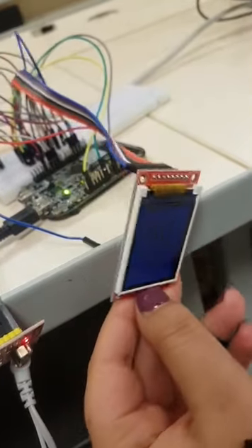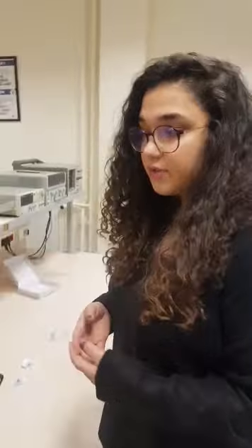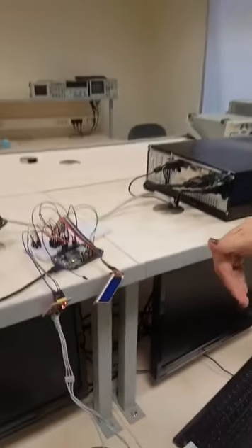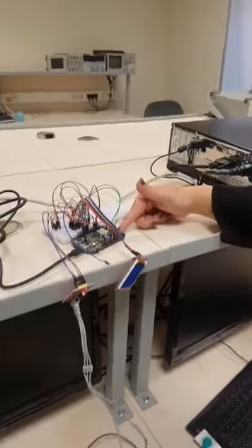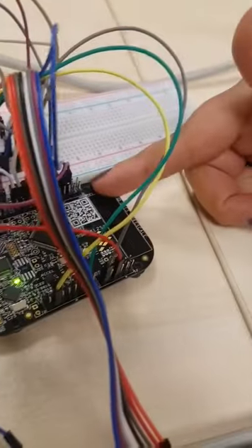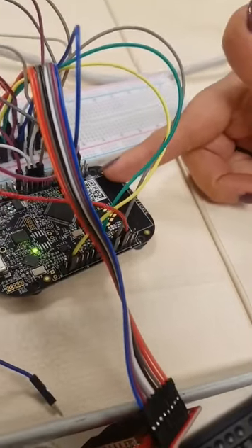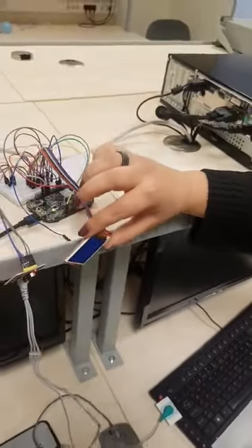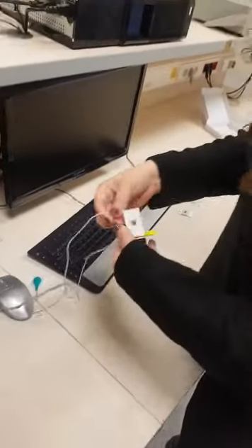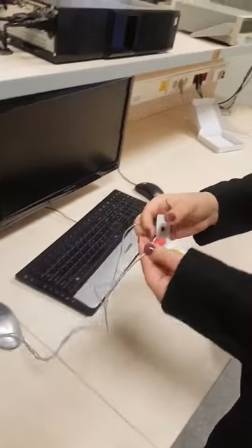On this LCD, we take 2 points of the analog signal, then we connect the 2 dots to make it an actual ECG graph. Then we show the heart rate and RR intervals on another screen, which can be controlled by going to the next page with this touchpad. As you can see, this is not working right now because there's not a constant heart rate coming from the pads.